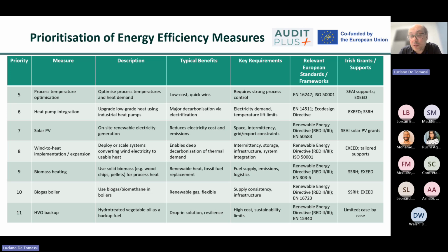With demand reduced and waste heat recovery maximized, facilities should assess opportunities to replace fossil fuel-based heating systems with more efficient electrical technologies. Examples include heat pump integration to upgrade low-grade waste heat and provide process heat, hot water, or space heating, electrification of thermal processes where technically and economically feasible, expansion of electric heating technologies to replace direct fossil fuel combustion. Heat pumps are particularly attractive because they can deliver multiple units of thermal energy for each unit of electricity consumed, significantly improving overall system efficiency.